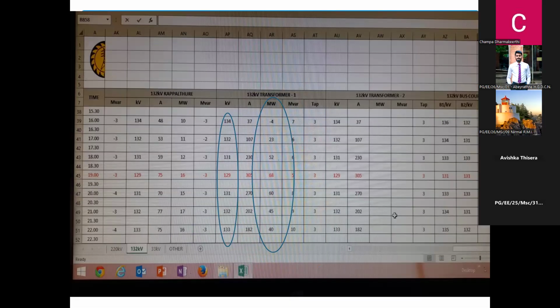This is not the reality only for the distribution network. This one is our transmission network. I will show you our new Anuradhapura grid substation, where we have 220 kV and 132 kV transmission lines ending up, and a few distribution feeders are going out.